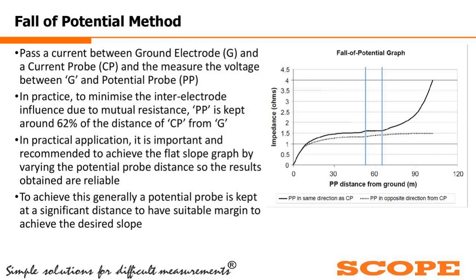Now, the second consideration: how much distance should I consider for putting the potential probe from the point of current injection? This is all nothing but the fall of potential graph. In this graph, as you can see, in between these two blue vertical lines, we are getting a flat zone. That is the base zone for the measurement of the earth resistance. So what is the distance? That distance is somewhere in the zone of 50 to 65 meters, or 50 to 70 meters.